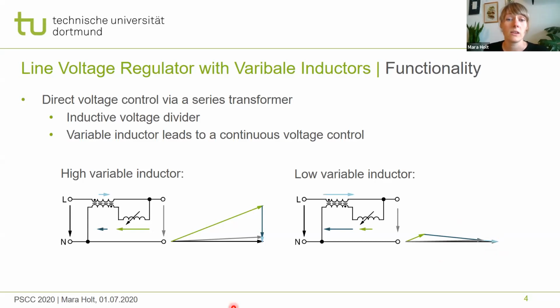The line voltage regulator uses an inductor in its cross branch. However, due to the series transformer, the voltage is adjusted via the amplitude and not via the reactive power flow. The inductor is used instead of a resistance to avoid joule losses.